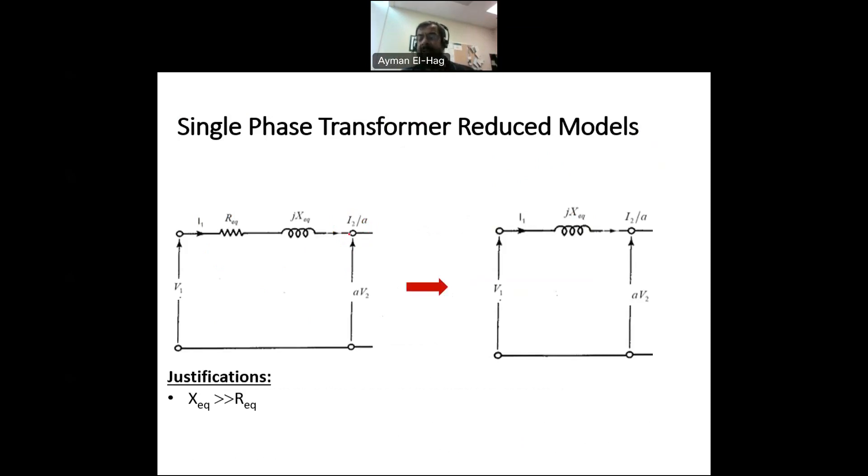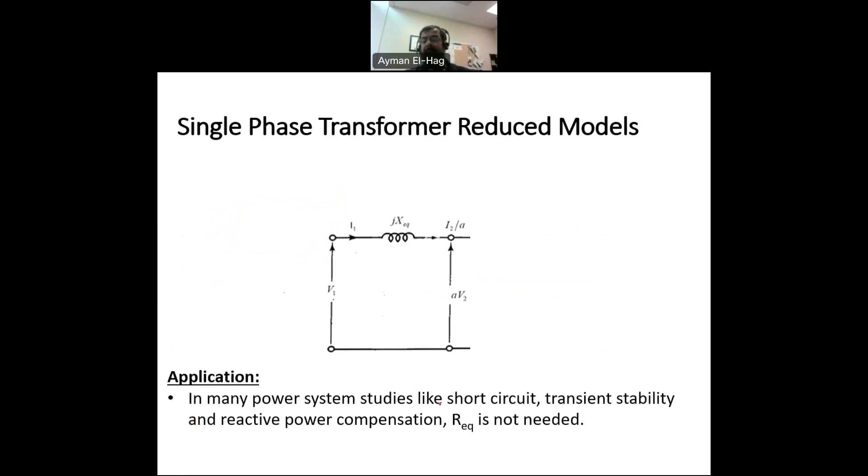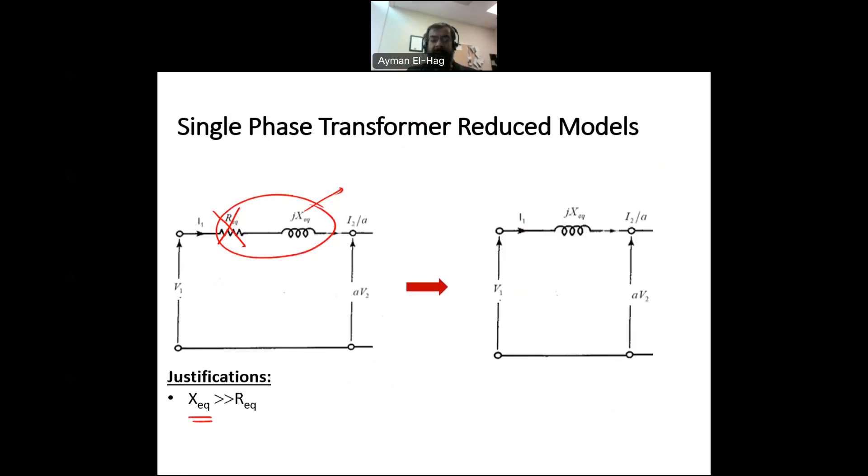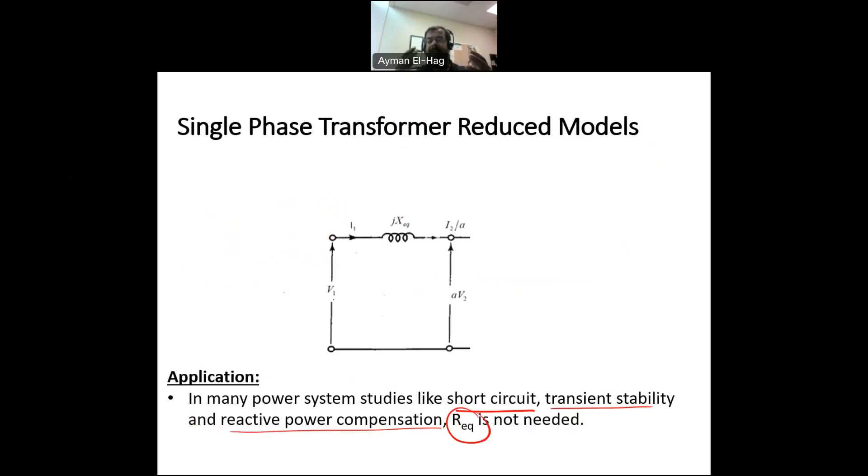The final model that we'll talk about today is that we can also ignore R equivalent. And the justification is that because X equivalent is much, much larger than R equivalent, so the voltage drop here is mainly coming from X equivalent. So we can ignore R equivalent. Now, where we can use this model, we can do it in different types of studies, like for example, short-circuit analysis, transient stability, reactive power compensation. R is not required in these models. So we can ignore R, knowing that X equivalent is much larger than R equivalent. Then this will not really impact much those studies.